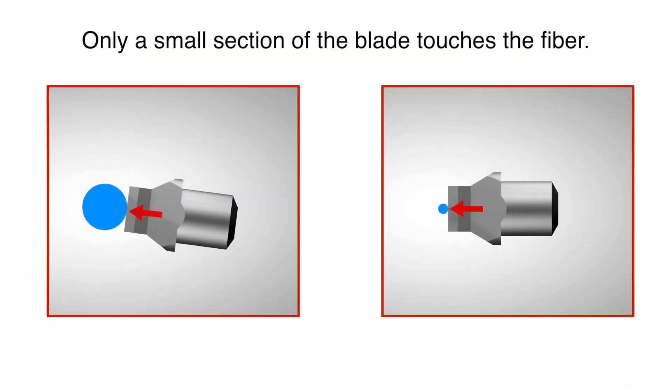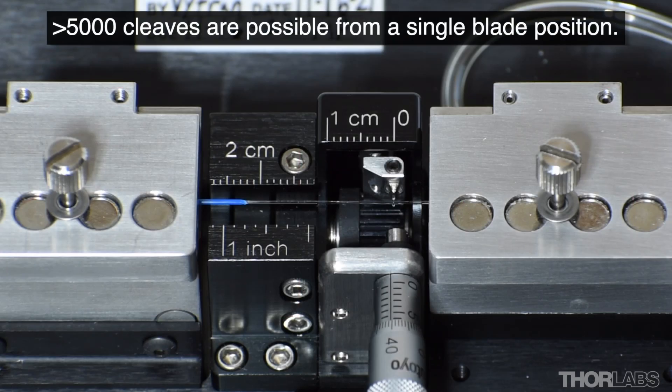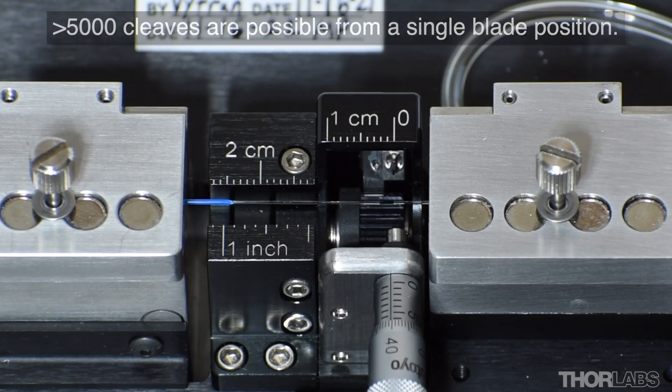During cleaving, only a very small section of the blade comes into contact with the fiber. A single section of the blade can remain sharp, producing good quality cleaves over 5000 times.